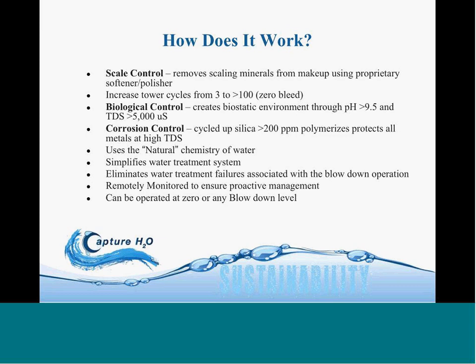So how does it work? As I said earlier, we're trying to control scale, corrosion and bacteria. Scale control comes from removing the minerals in that water. So whether it be groundwater, rainwater, recycled water, or city water, the system removes all the scaling minerals before they get into the cooling towers. This allows us to remove the limits on how high you can concentrate that water, and we can run from any level of blowdown to zero blowdown if we wanted to. So scale control comes from removing the minerals in the water beforehand.